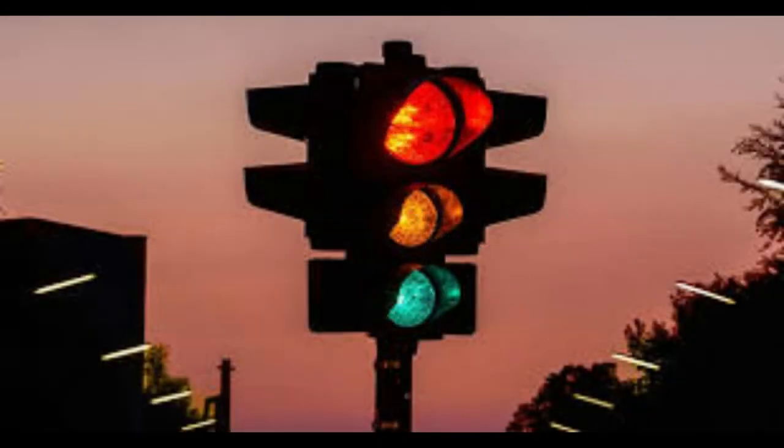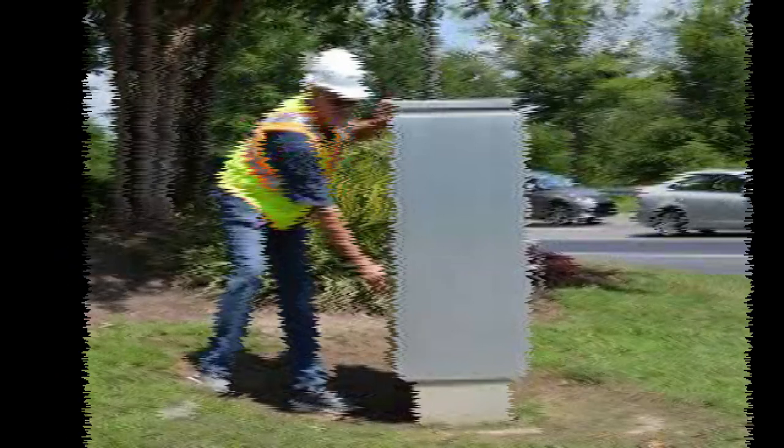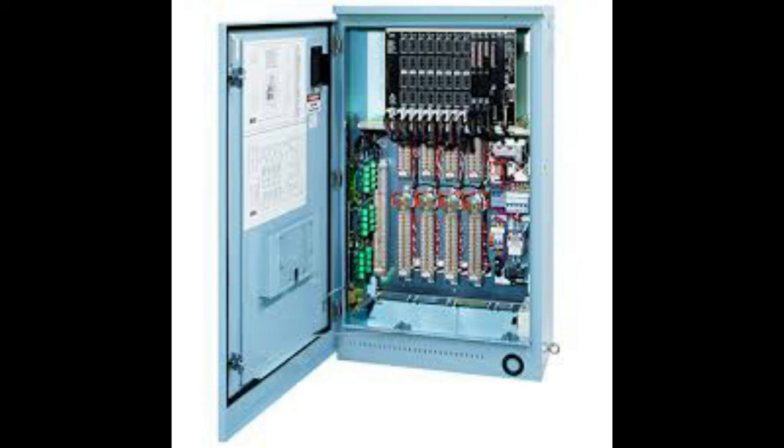A traffic signal is typically controlled by a controller mounted inside a cabinet. Some electromechanical controllers are still in use. However, modern traffic controllers are solid state. The cabinet typically contains a power panel to distribute electrical power in the cabinet, a detector interface panel to connect to loop detectors and other detectors such as detector amplifiers, the controller itself, a conflict monitor unit, flash transfer relays, a police panel to allow the police to disable the signal, and other components.